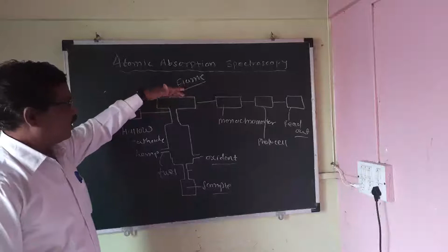The light source is a lamp whose cathode is composed of the element being measured, and each analyzed element requires a different lamp. For example, for aluminum, an aluminum hollow cathode lamp is used. The cathode lamps are stored in a compartment inside the atomic absorption spectrometer, and the specific lamp needed for the given metal analysis is rotated into position for a specific experiment.